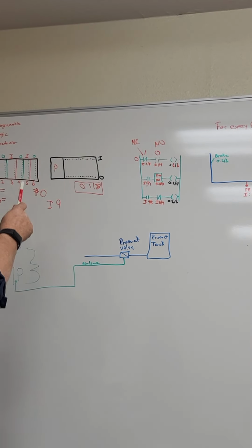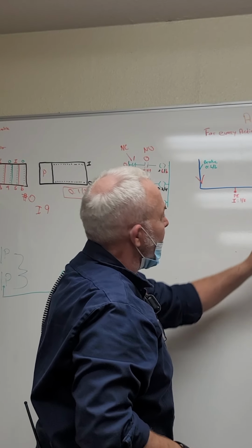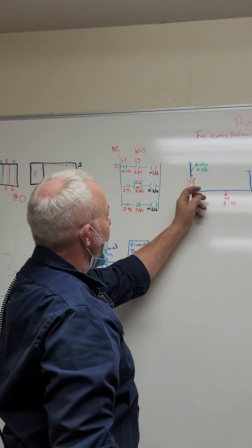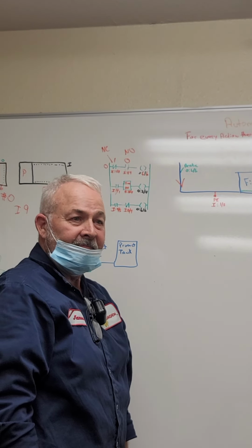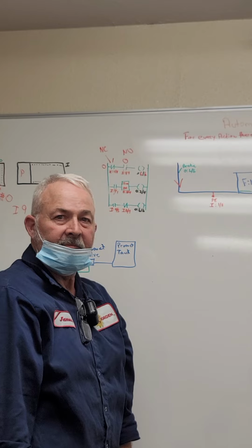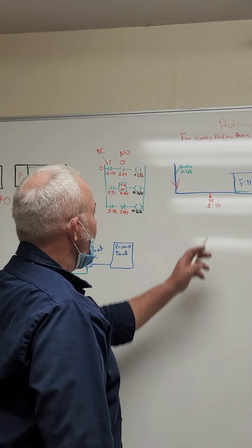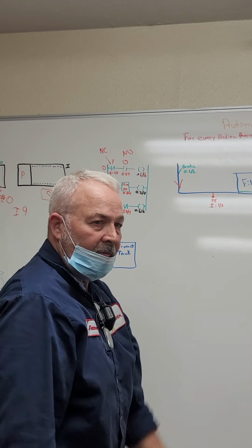Your flow is this way, because this is the infeed of the filler, but your photo eye is down here, and we're working backwards. It's blocked. There again, an action makes a reaction. This photo eye gets blocked, which means the line is full, so it hits the brake to keep from overfeeding the filler.